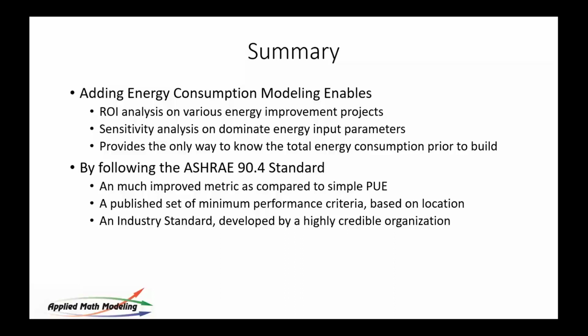Furthermore, the new ASHRAE spec is going to ask us as designers to look at that at 4 different points. What's it look like at 25? What's it look like at 50, 75, and 100? Not just 100. The historical method we've used is build for worst case loads. And what we found in the data center business is we're not seeing worst case loads. That's because the energy efficiency of the IT equipment itself has gotten better over time. They're running at lower voltages, they're using less power. Now that will eventually catch up, and then we'll get back on that same curve of increase again.